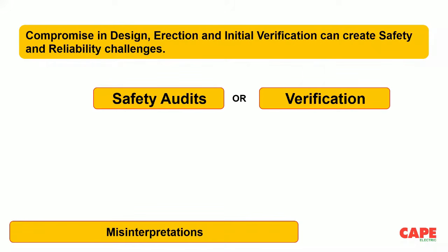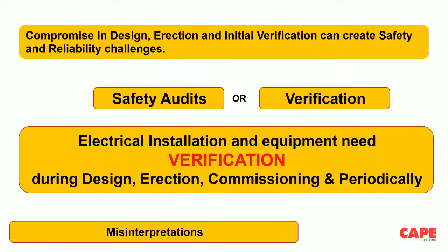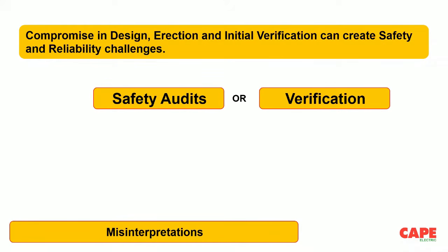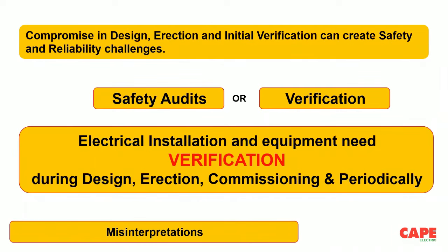So whatever we do on a sampling basis can be called an audit, and whatever we do thoroughly is verification. For example, fire safety. It's not fire safety audit. It is fire safety verification. So please refer to the necessary standard. You will be able to understand the meaning and the complications of this particular standard. The difference between audit and verification is, in a verification, you are supposed to inspect and test all the points. In an audit, not all the points, according to your convenience. So the auditor can decide the amount of things which he is supposed to do, whereas in a verification, he cannot make that decision. He has to go as per the standard, because for electrical or fire installations, we are talking about the safety of people.